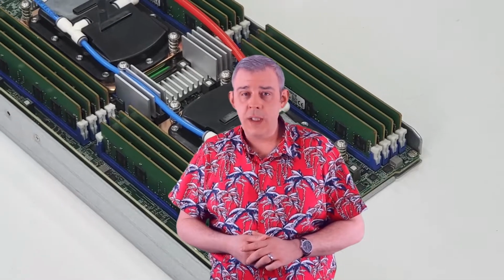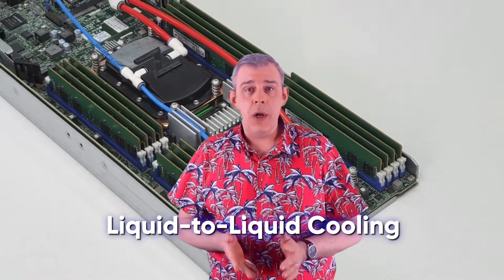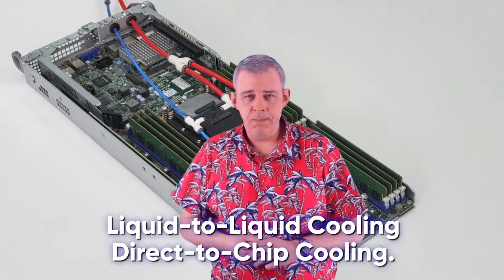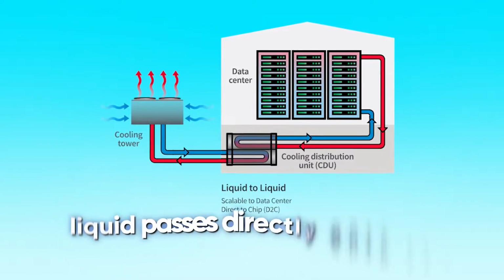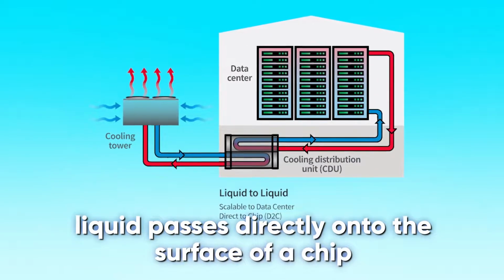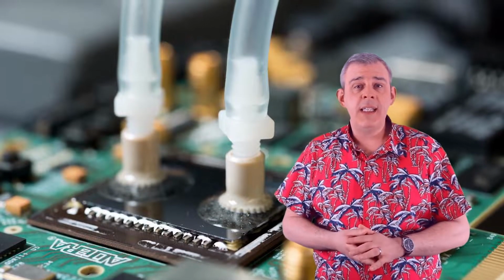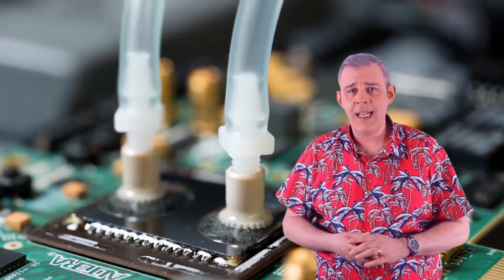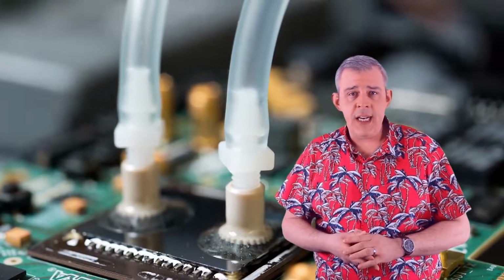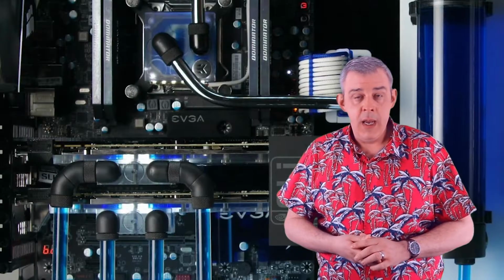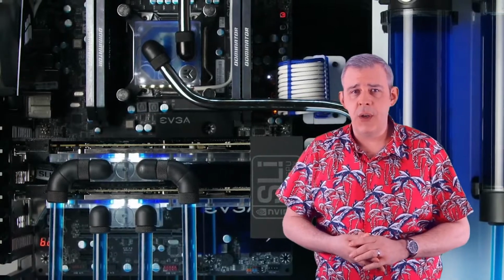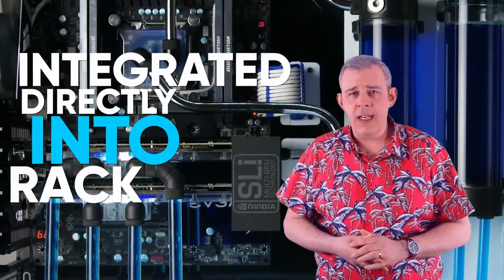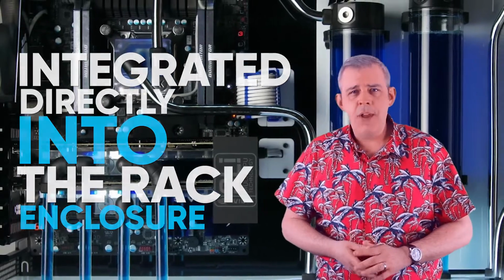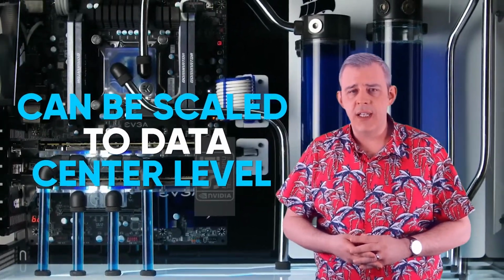Supermicro utilizes a variety of liquid cooling methods for their systems. The first is liquid-to-liquid cooling, also known as direct-to-chip cooling. With this configuration, liquid passes directly onto the surface of a chip, drawing heat away. This liquid is then cooled through a liquid-to-liquid heat exchanger that can be integrated into a rack or contained externally. This is a great choice for space-sensitive solutions, as the exchanger can be integrated directly into the rack enclosure, though if required it can be scaled to data center level.